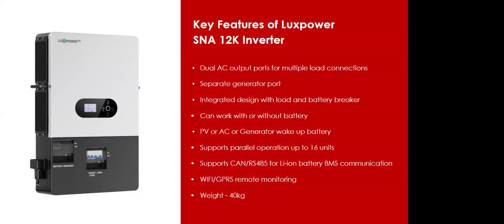Now it supports CAN and RS485 for lithium-ion battery BMS communication. Some batteries don't have a communication port, and some do. For those that have it, the port is already there on the inverter—just connect and program it to link them up and make them communicate. It makes life a lot easier because you'll be able to effectively use the battery to its maximum recommended capacity.